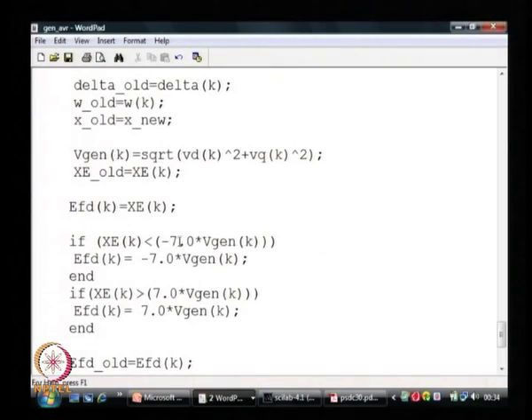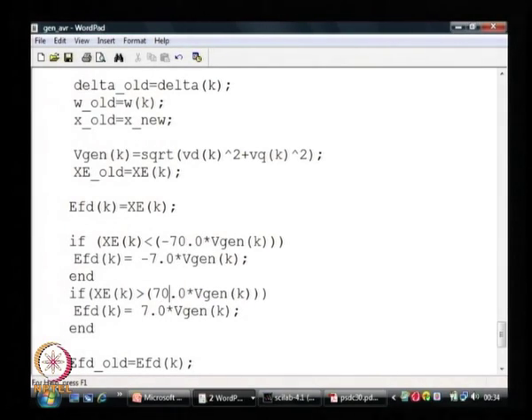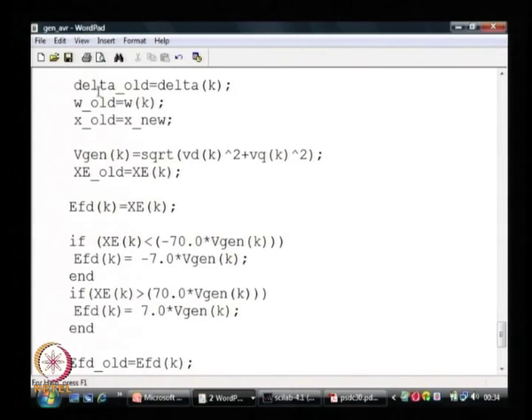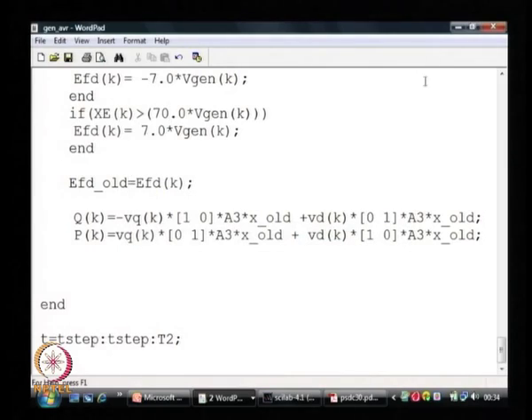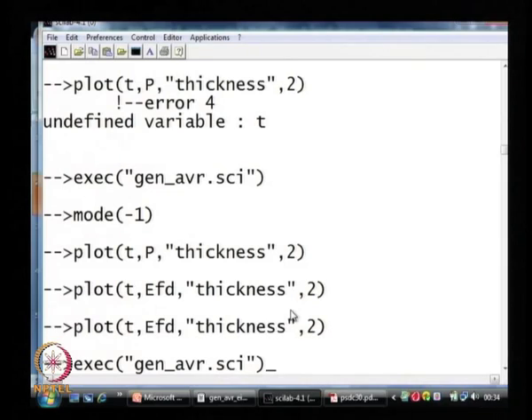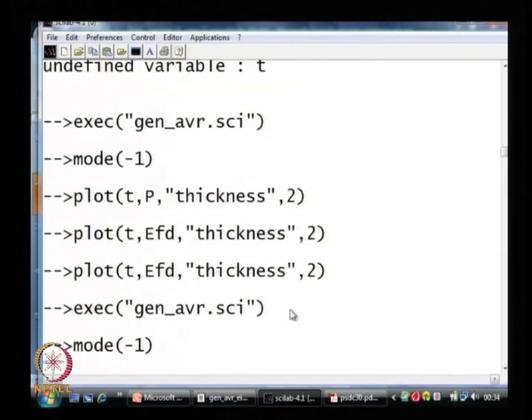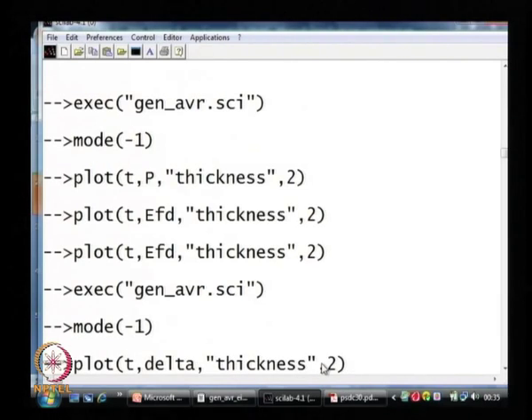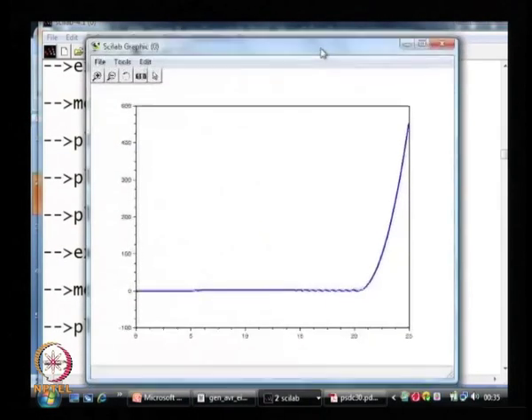In case I remove this clipping action—if I remove the limiters in the model—what happens? What I will do is make the limits very, very large, which practically disables them. Instead of 7 times the terminal voltage, Efd is limited to 70 times—a very large value, so the excitation system is for all practical purposes unlimited. I rerun the simulation with unlimited field voltage capability, and plotting the rotor angle delta, we get an altogether different behavior.